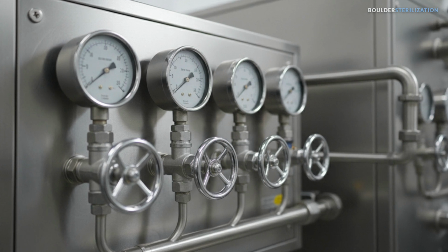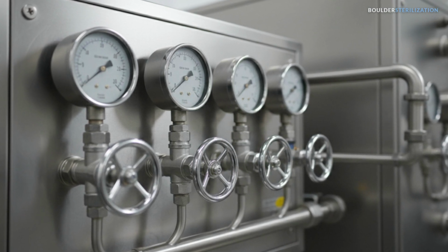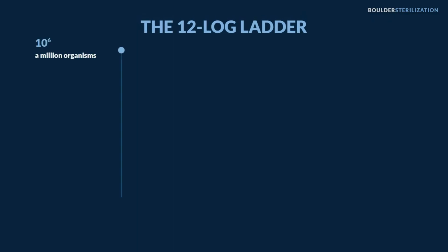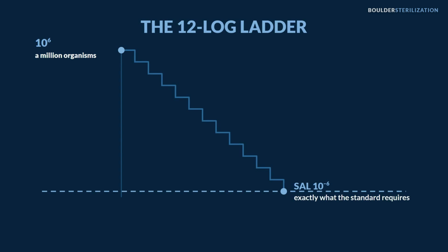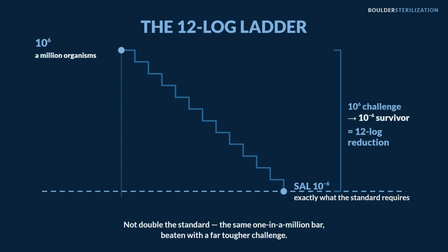If every one of those million spore indicators comes back with 0 growth, complete kill, we've demonstrated at least a 6 log reduction at half the dose. Now the full cycle. Your production cycle runs twice that exposure. The half cycle already wiped out a 1 million spore challenge. So across the full cycle, you're looking at least a 12 log reduction from 1 million organisms, 10 to the 6th, down to a 1 in a million chance of a single survivor, 10 to the -6.